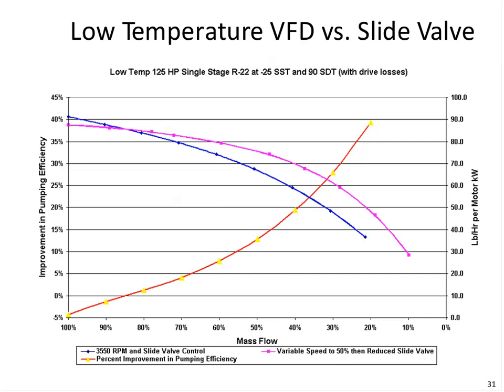So these are screw compressors with slide valve and variable frequency drive. Here we're at minus 25 degrees, single stage, 125 horsepower compressor. And we've got two curves on here representing compressor power or pumping, and we're expressing that in pounds of refrigerant per motor kW. So the more refrigerant compressed per kW, the more efficient it is.